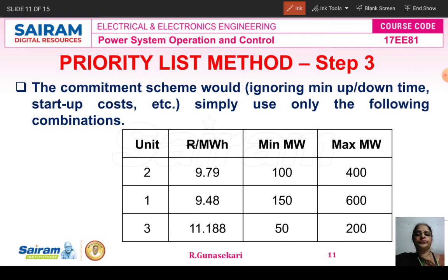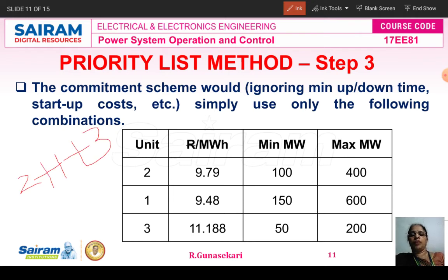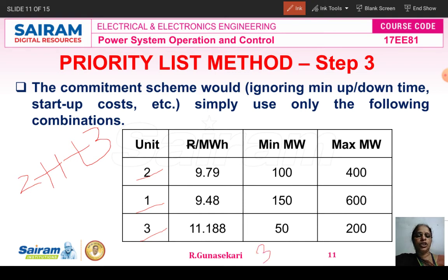Now, what are the combinations? The priority order is unit 2, unit 1, unit 3. From this, we can prepare the combinations. The first combination is 2+1+3. The minimum generation for this combination is 100+150+50 = 300 MW. The maximum generation for this combination is 1200 MW.